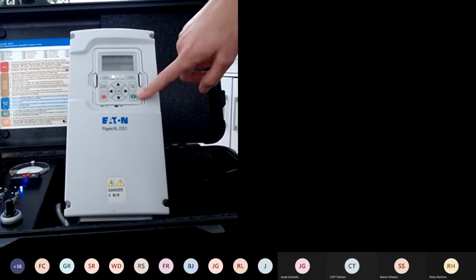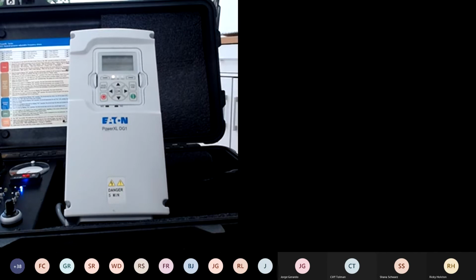can be operated a few different ways. It can be operated through hand control, remote control through IOs, or control through your PLC system directly onto the VFD, so Profibus, Ethernet IP. Make sure you have the right card selected when designing and installed when connecting onto the systems. Your VFDs have some excellent capabilities for PLC control. They can also do some multi-motor applications, and there's just a lot you can do with a VFD.